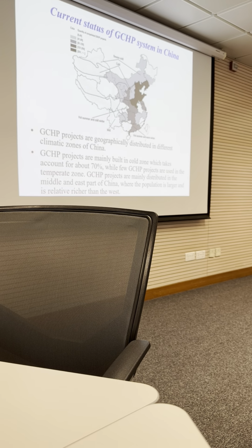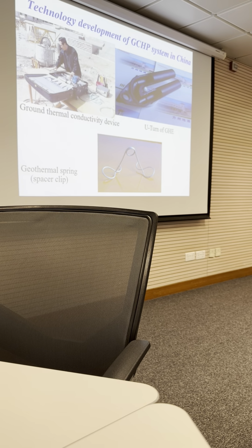It's expensive, maybe. Early on, Shandong University in fact started research in China about 30 years ago, and they conducted the first system in Jinan. They developed the U-tube ground heat exchange pipelines and did the thermal conductivity test, the thermal response test. The location is in Jinan, Shandong province, about 25 years ago, to supply hot water for space heating in winter and cold water for air conditioning in summer.